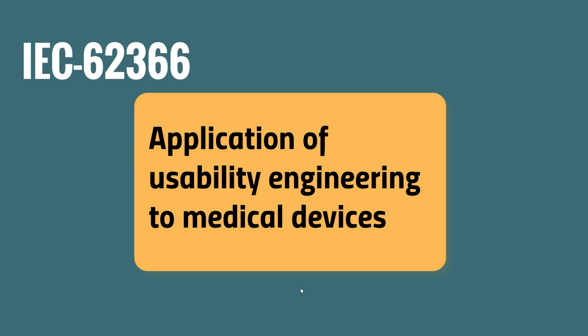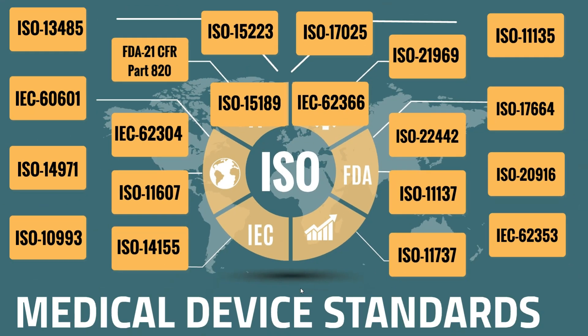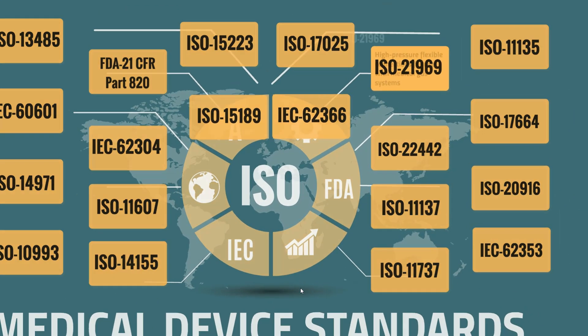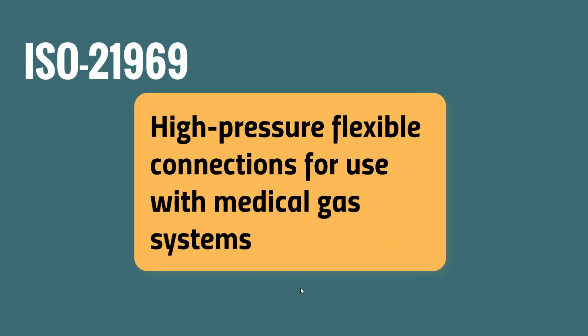13. ISO 21969 — this standard applies to high-pressure flexible connections intended to connect cylinders or cylinder bundles to manifolds within sources of supply of medical gas pipeline systems.